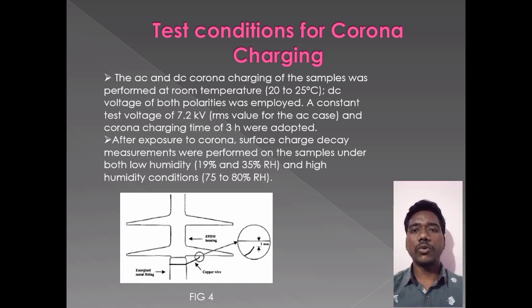This consisted in exposing the EPDM housing of an actual 15 kV class non-ceramic suspension insulator to impinging corona, and characterizing the PD and frequency with application of both AC and DC high voltage. To facilitate corona generation, a copper wire of approximately 0.2 mm was attached to the energized metal fitting of the insulator, which is shown in figure 4. With this electrode configuration, the corona discharge path was simulated by a copper conductor whose tip was situated 1 mm away from the weathershed bottom surface.